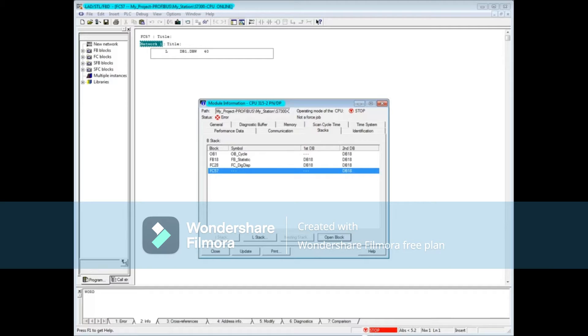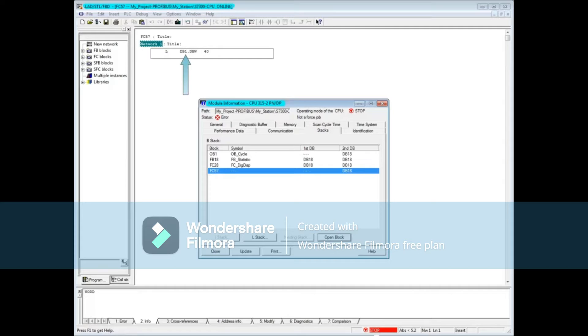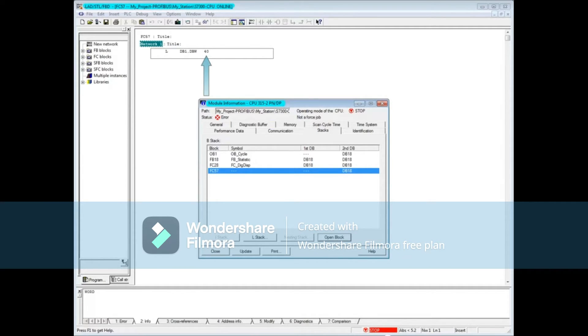There is only one line of code for this demonstration so the problem either has to be that data block 1 is not loaded into the CPU or else there is no word 40 in data block 1. A visit to the diagnostic buffer tab will tell you which it is.